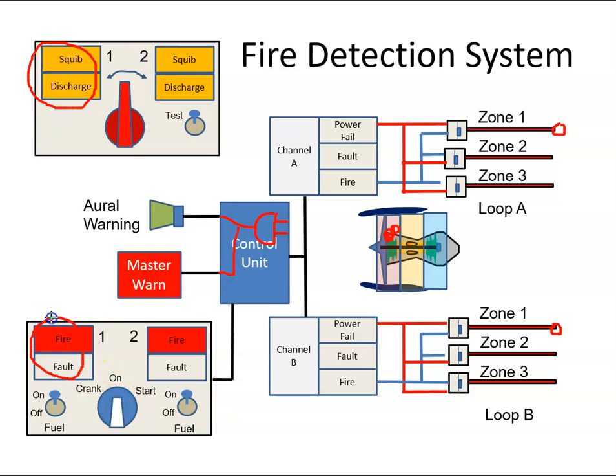That's the different zones. Just to note that whatever sensor you use, it's particular to that zone and they may not be interchangeable, or you may have to do some calibration with them, just because the normal operating temperature differs from zone to zone.